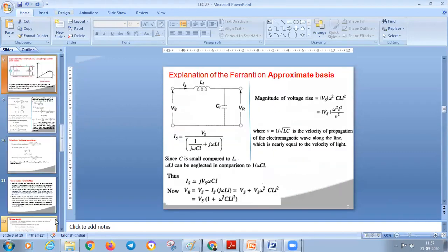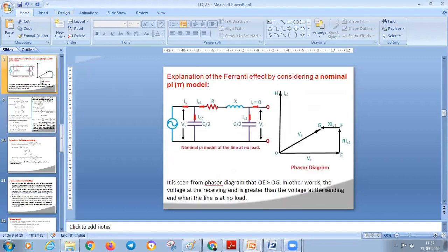From the expression for Ferranti effect derived from the nominal pi method, the Ferranti effect depends upon the square of the frequency and the square of the length of the transmission line. From the approximate analysis method also, the magnitude depends upon the square of length and ω (angular frequency). So the Ferranti effect depends on square of length and square of frequency.